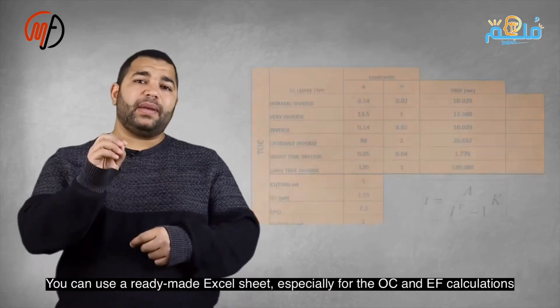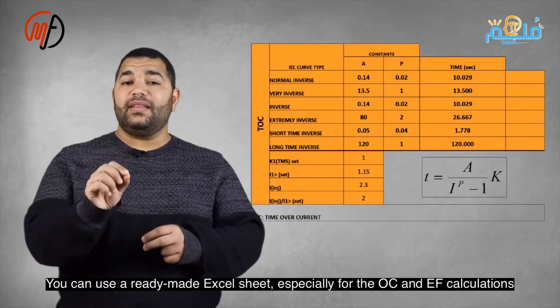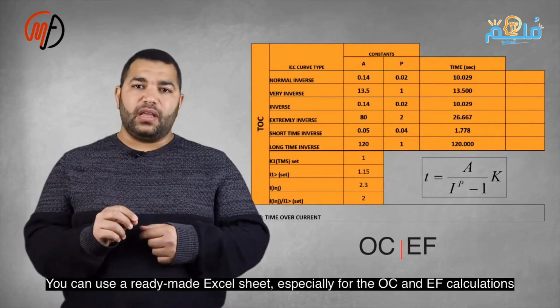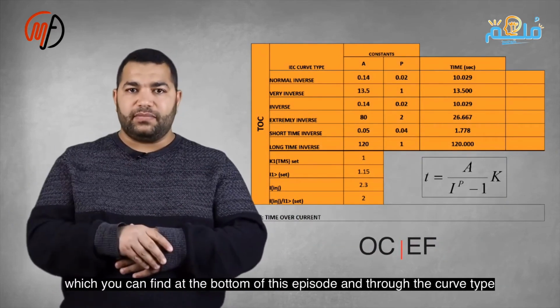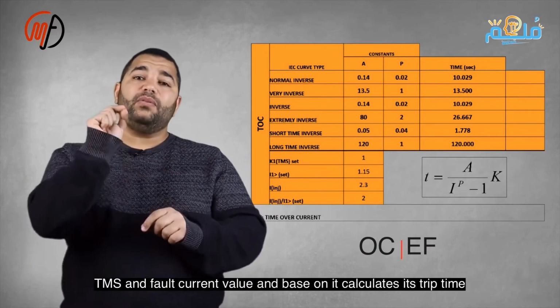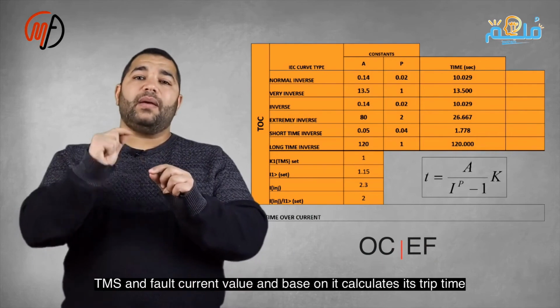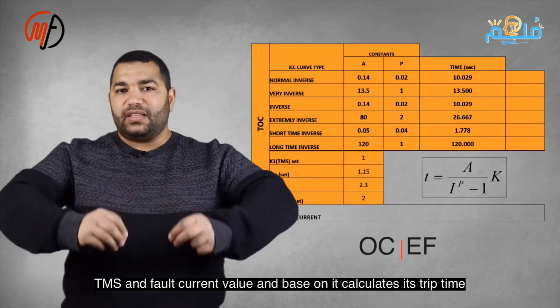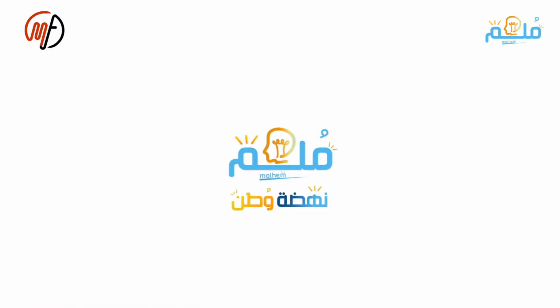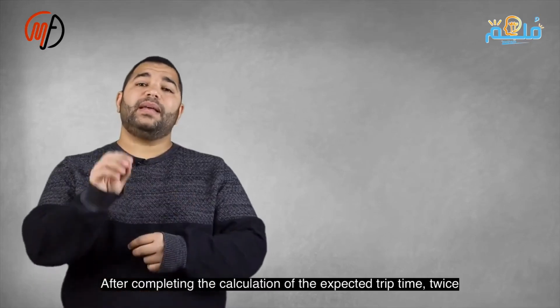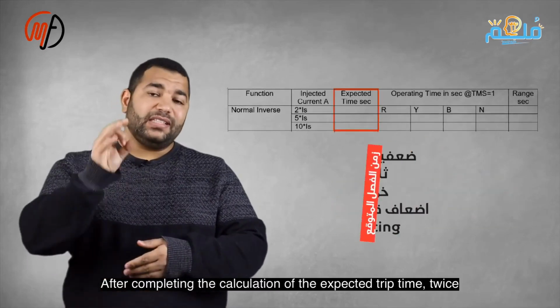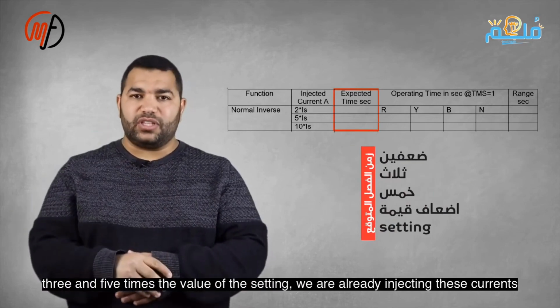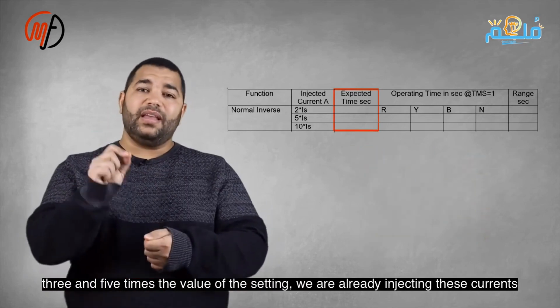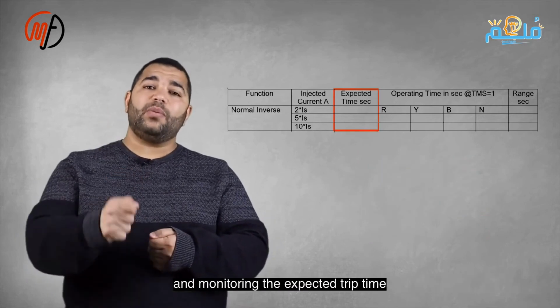You can use a ready-made Excel sheet specifically for calculating the trip time for overcurrent and earth fault, which you can find below this episode. In this sheet, you can input the type of curve, the TMS value, and the fault current value, and it will calculate the trip time for you. After calculating the expected trip time at multiple settings, we inject these currents and wait for the trip time, comparing it with the calculated time to find the error percentage.